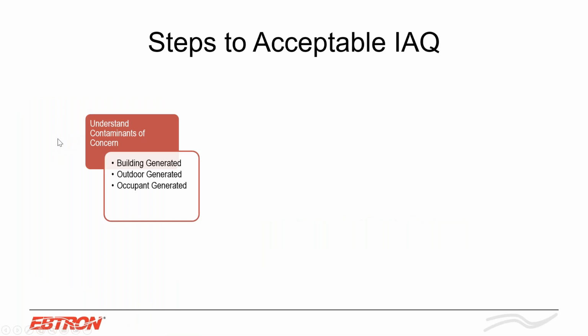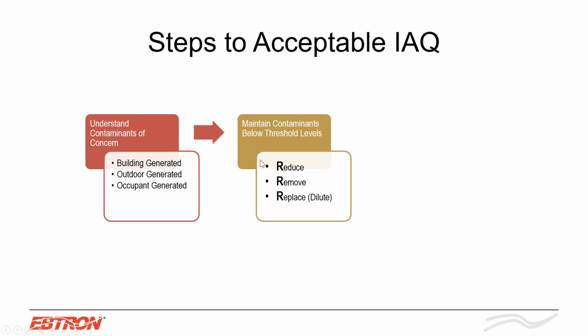So here are the steps to acceptable indoor air quality. The first thing you've got to do is know what the contaminants of concern in the space are. So you have building generated, you might have VOCs based on the building materials in the space. You have outdoor generated, and you have occupant generated, right? Well, you want to maintain those contaminants below threshold levels. So I have this as the 3 R's: reduce, remove, replace, but really it's dilute. And that's where EBTRON comes into play with dilution ventilation.